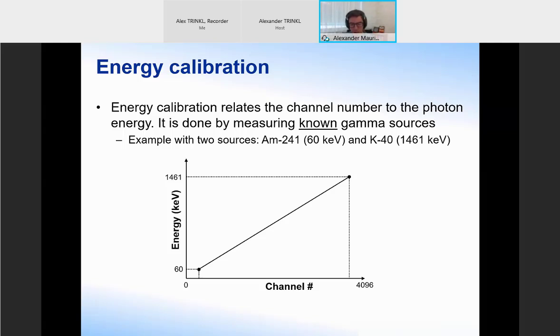And of course, when you choose the total number of channels available, and when you choose approximately which channel you want to see a certain type of peak in, that depends on which energy range you are looking at for your measurements. You can make adjustments to your electronics to make sure that the full range of your spectrum covers the energy range that you are interested in for your measurements.